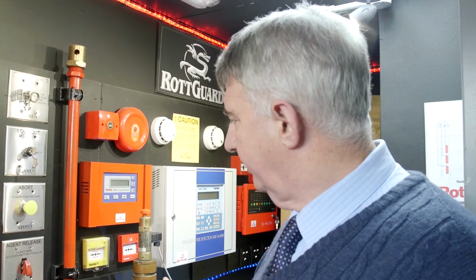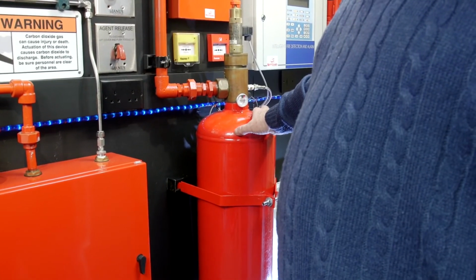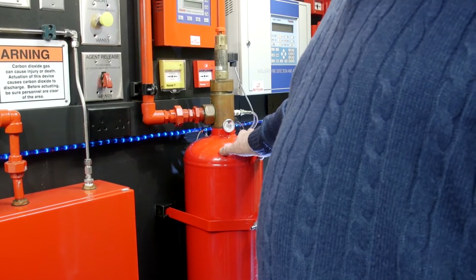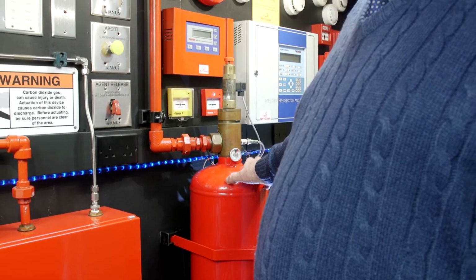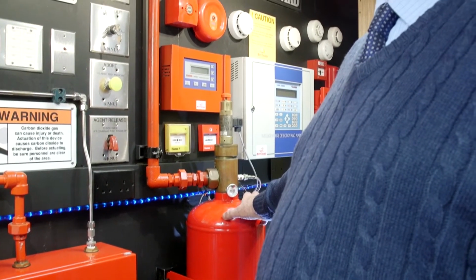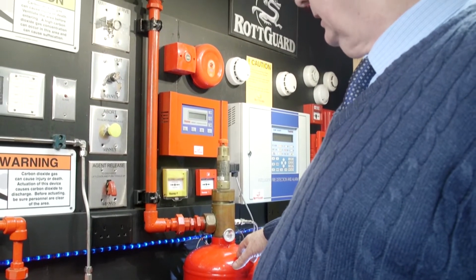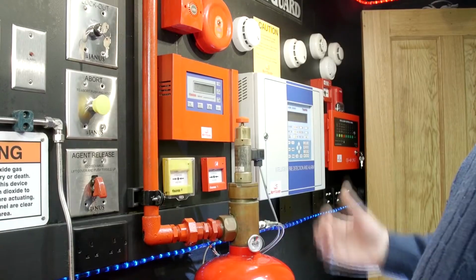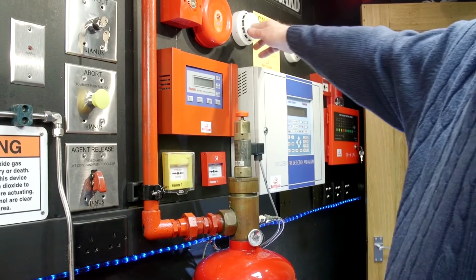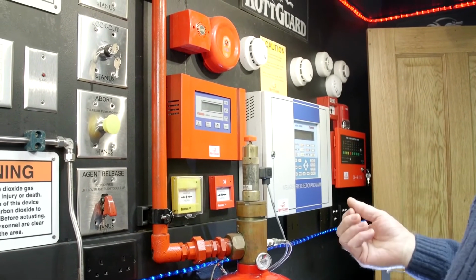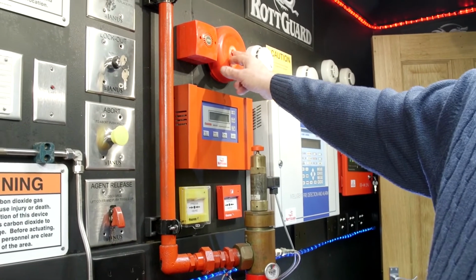This is a representation of a clean agent fire suppression system commonly used to protect the whole of an electrical room, server rooms, comms rooms, archives, and so on. They use one of two agents, either FM200 or Novec, both of which are the most commonly used agents to protect such risks. In the event of one of the smoke detectors picking up smoke in the room, it will activate this bell.